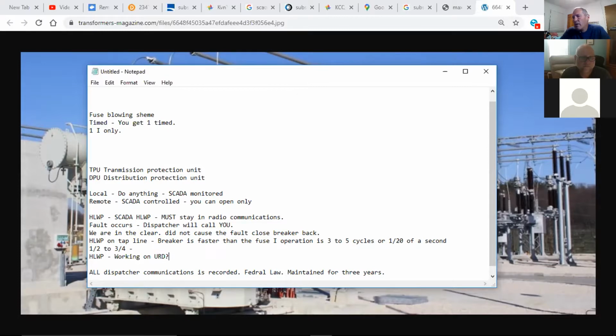There's live underground primary on my site. Exposed? When I say, working with my underground primary through my URD site, is there any exposed live, underground component while I'm working on it? No, just in the enclosure. What live part do you see in the enclosure that is exposed, that I can physically touch? The feed-through elbow? I'd have to manually stick something down inside the elbow to touch something energized. Right, so that's not truly exposed. What else, the panel that's in there? You're talking about the four-way module? Yeah, I'd have to take a clothes hanger or something like that and stick it down in the insert for me to be exposed. That's covered also.